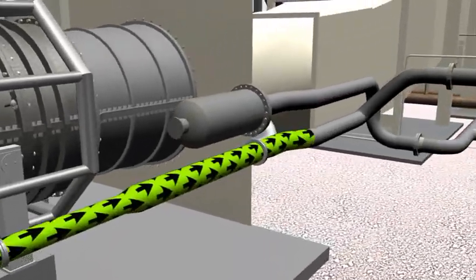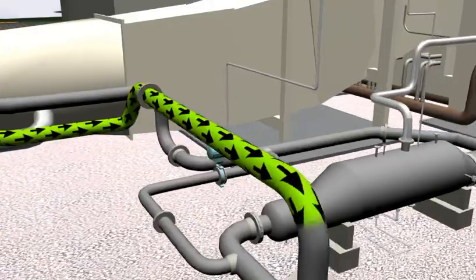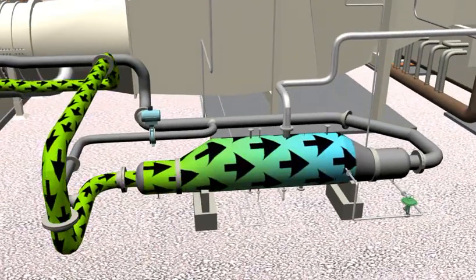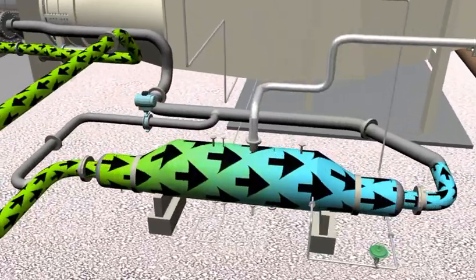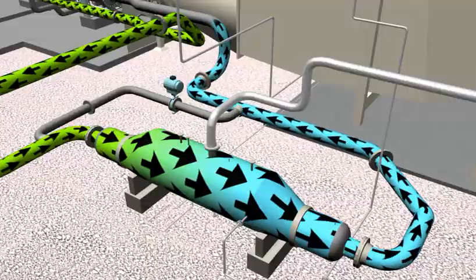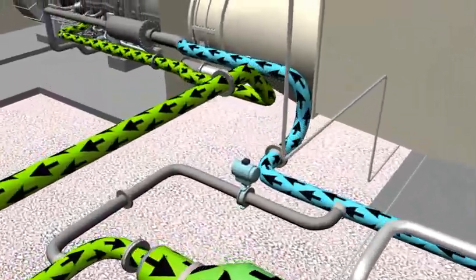About 35% of the compressor air is bled off to the rotor air cooler or kettle boiler. The cooling medium for the kettle boiler is water supplied from interstage feeds from the boiler feed pumps. The hot compressor air changes this water into steam that is then sent to the low pressure drum on the HRSG.